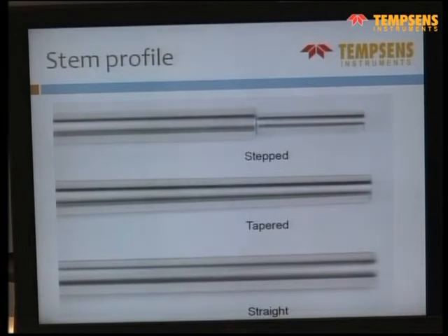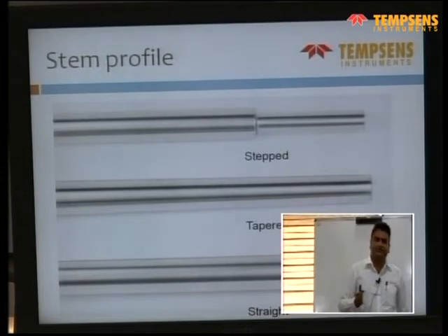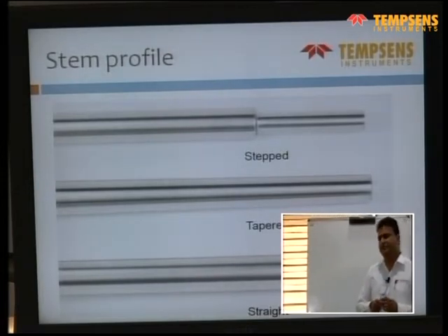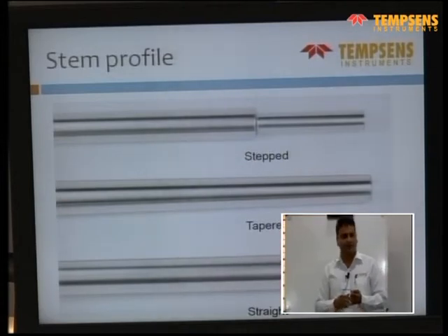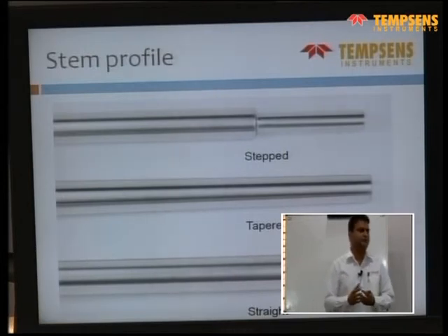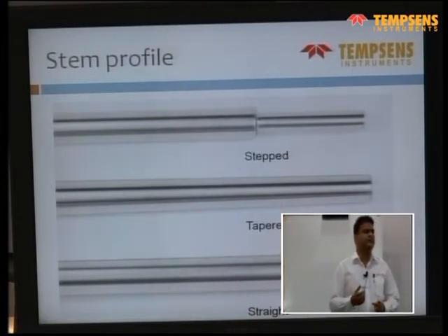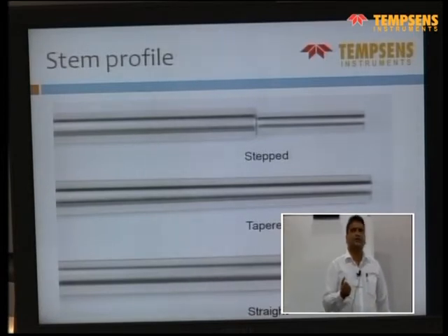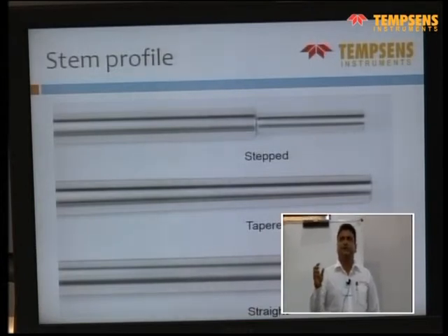These are the stem profiles. You can have a stepped profile, which has the advantage of better response time. All temperature sensors, whether RTDs or thermocouples, measure their own temperature. So the RTD or thermocouple has to get heated up to give a proper temperature response. In a stepped thermowell, the volume to be heated is smaller, so it gives a faster response time than a straight construction.